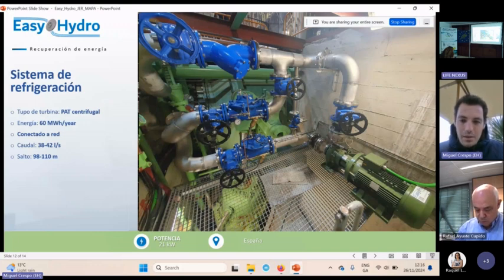This system is quite interesting because the output power of the 40 megawatt turbine was capped, since the alternator suffered overheating in some points. With our system, we allowed the hydro operator to regulate the flow going to the alternator and improve its cooling. After the commissioning, we made some tests with the main turbine at 100% of its capacity. We improved the thermal efficiency of the system by more than 20%, and the turbine was running at 100% of its capacity for 8 hours in a row.